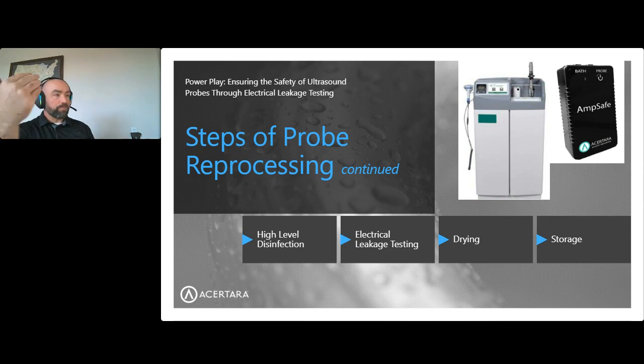You may have an automated disinfecting station. Typically, they're going to ask you if the probe passes electric leakage before you do the high-level disinfection. And of course, you want to record that data each time, right? It helps when we have data to keep from having to deal with all the finger pointing that you might see when something does go wrong. You can show them the steps that you took and the values that you got when you actually made the measurement. Some automated high-level disinfecting stations have an electric leakage tester attached to them, or an electrode that's built in, and you can hook up any electric leakage tester that you want to. Some are better than others, so make sure you do your homework there.